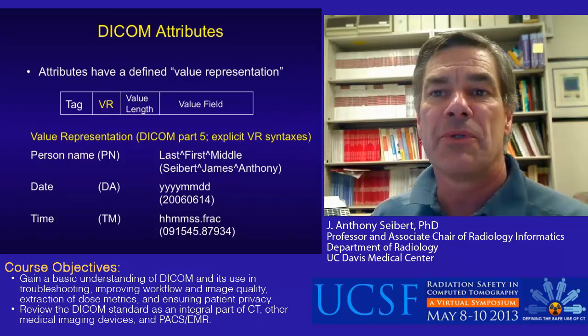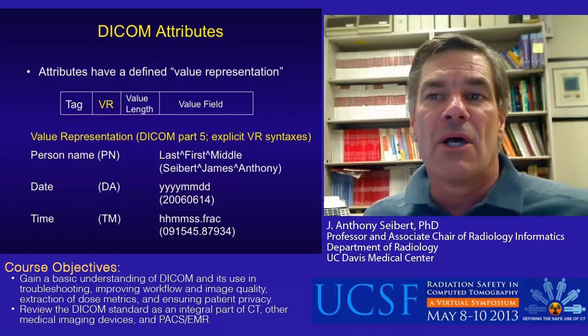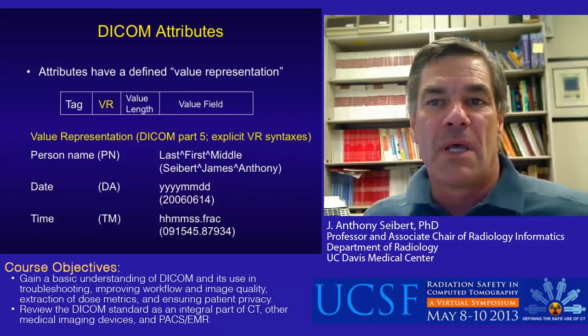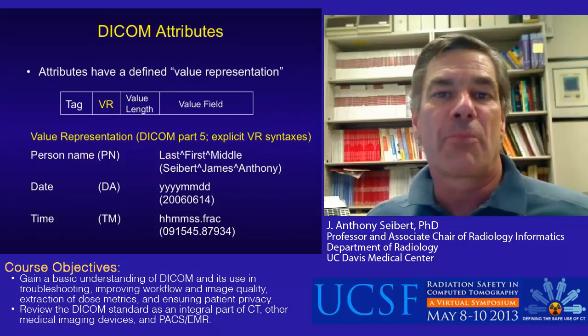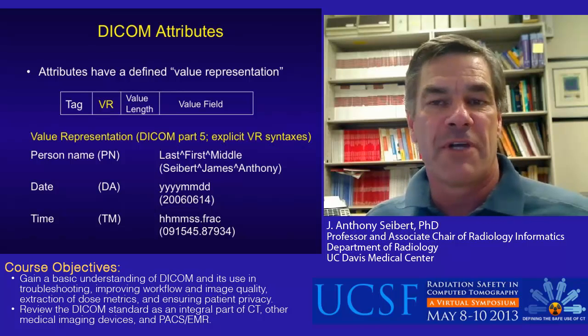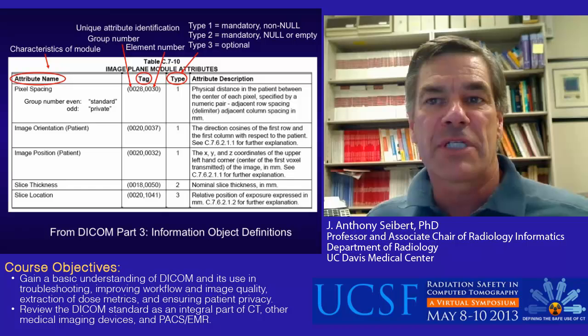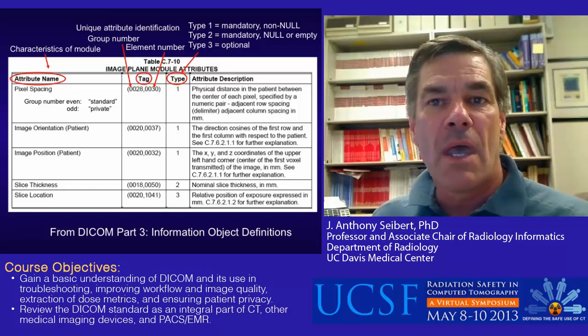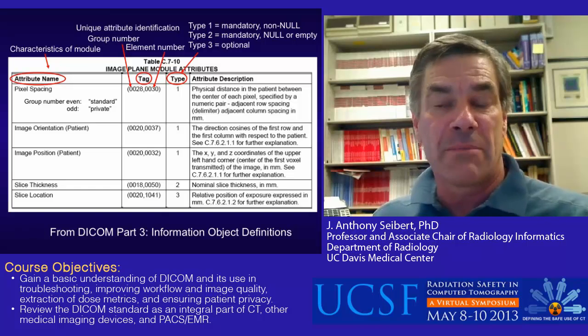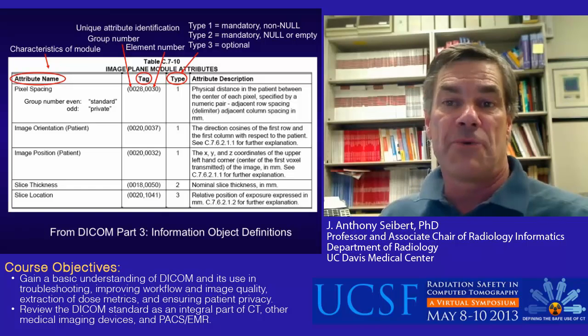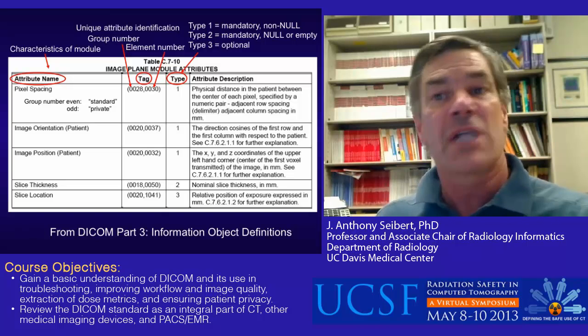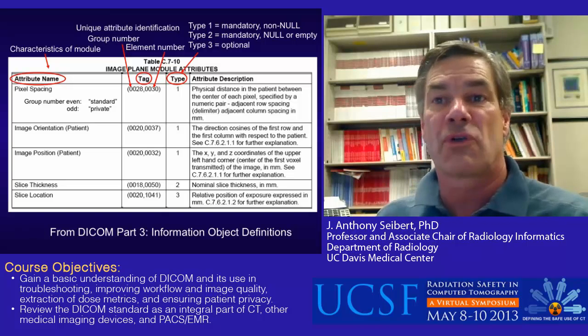An important part of an attribute is the DICOM tag, shown as a group number, comma, element number pair which uniquely identifies the attribute. Tags with an even group number are public and tags with an odd group number are private, mostly for proprietary use by the vendor. DICOM also requires a type field identifying the attribute to be mandatory and filled in as indicated by a 1, mandatory and either filled in or left blank as indicated by a 2, or optional as indicated by a 3. Examples of pixel spacing attribute, image orientation, image position, slice thickness, and slice location are shown with descriptions.